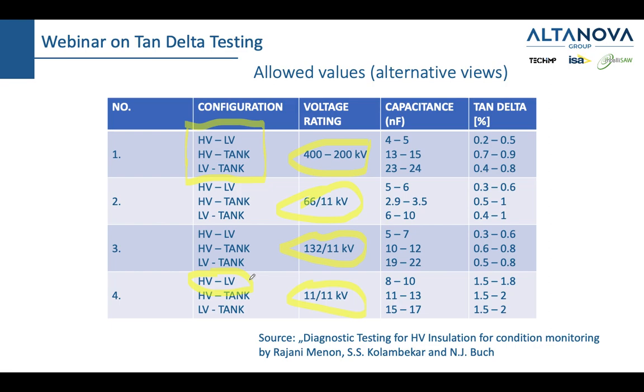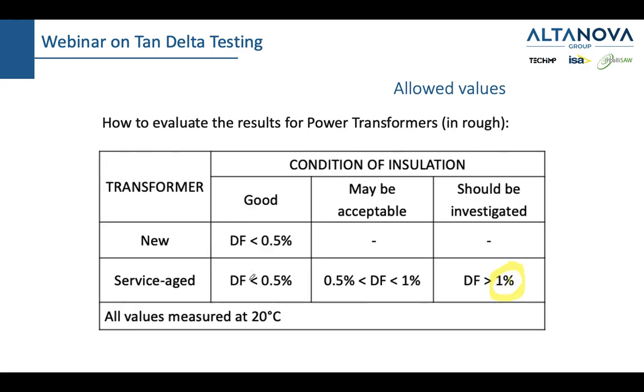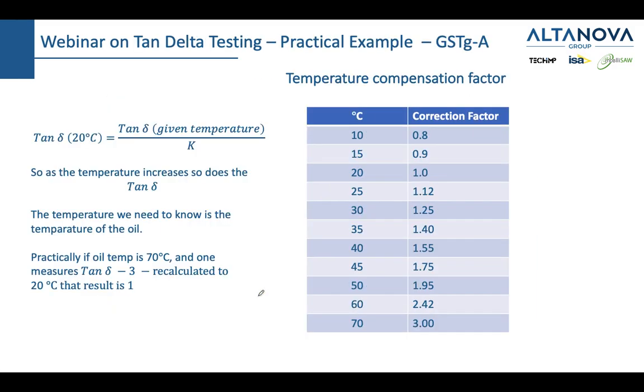So Sirtel asked, is there some standard about tan delta level for high voltage transformers? So I hope this is answered by this slide here. And another thing I want to answer is, I haven't mentioned before that all these values are at 20 degrees Celsius. Tan delta depends on temperature. It's temperature dependent. And we can see here what the formula is, how to recalculate tan delta onto 20 degrees Celsius.